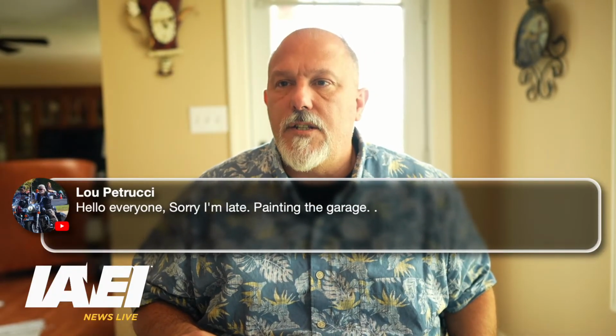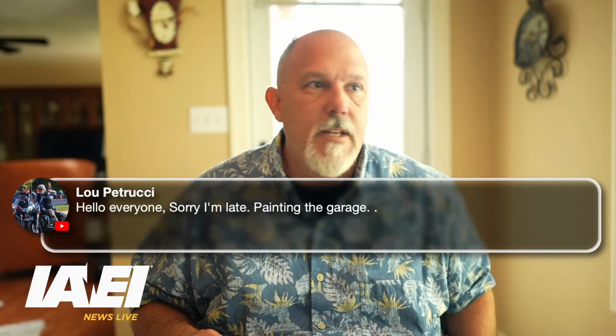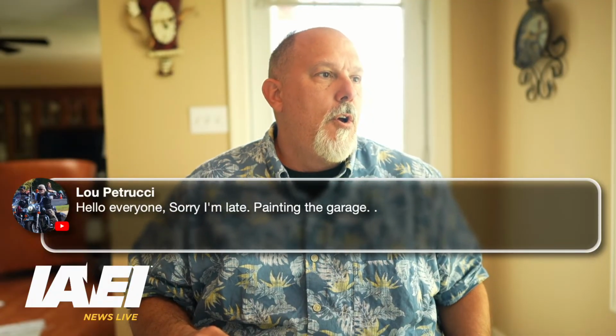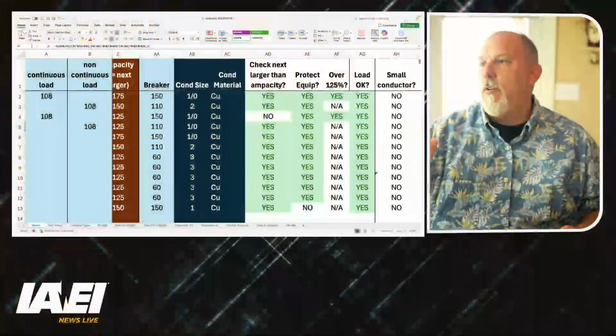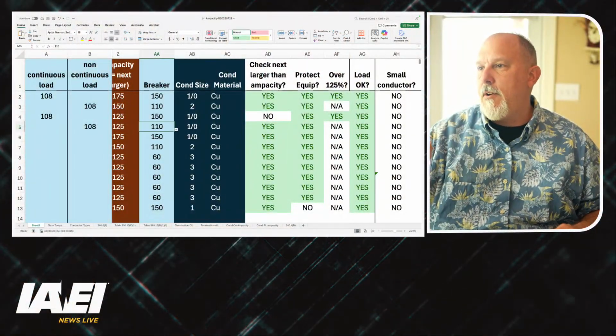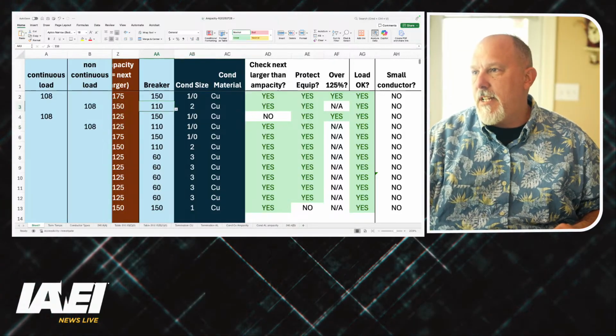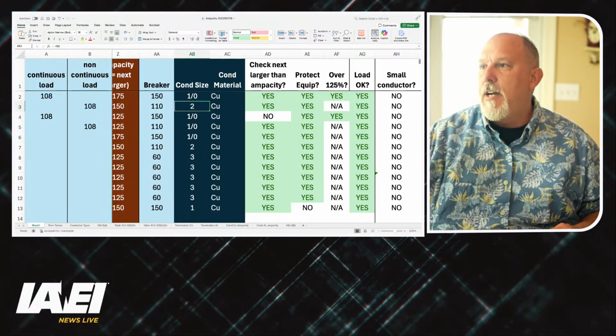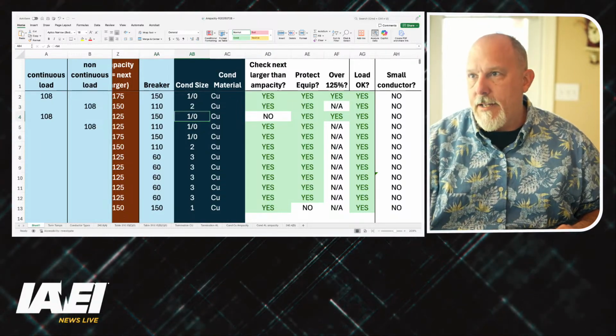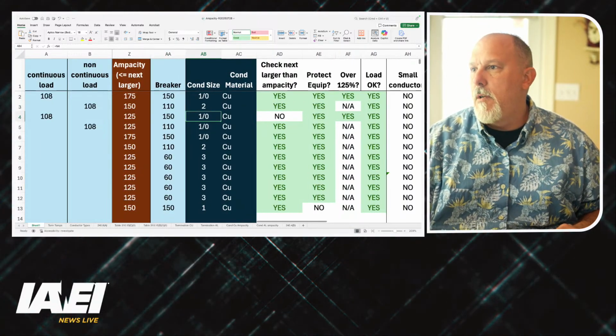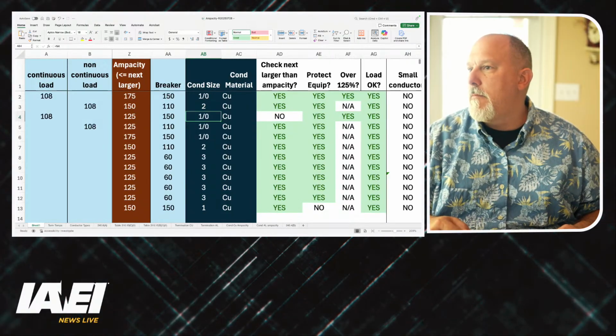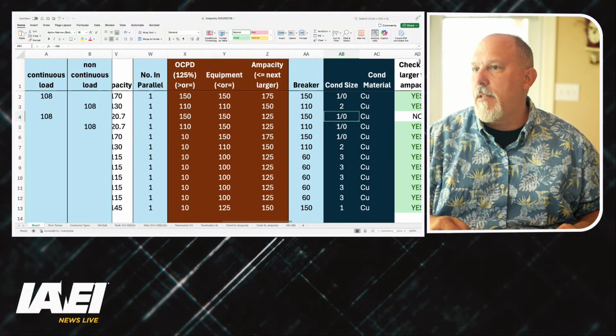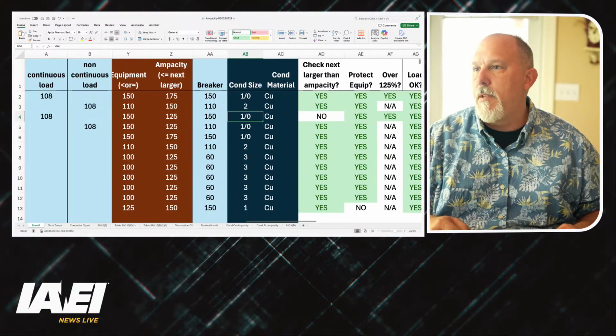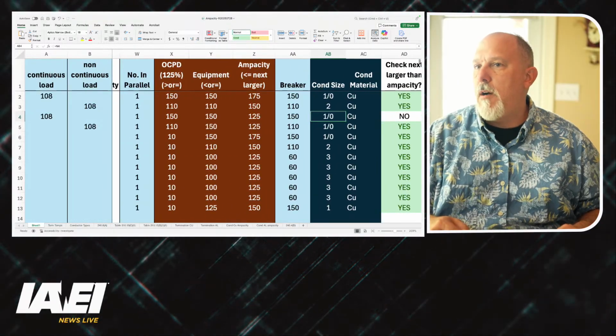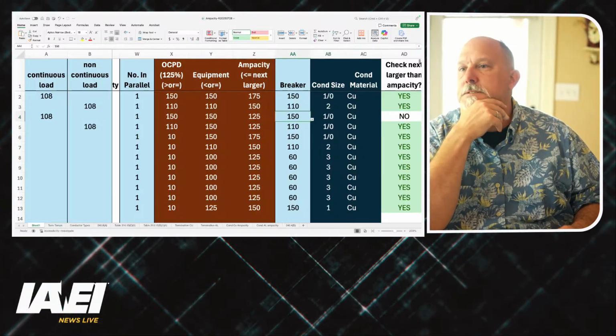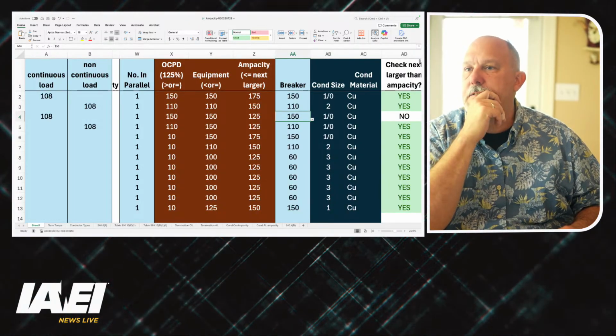Ugh. All right, so I'm going to go to UL 489. Just to refresh your memory, we have a 110 amp breaker on a 1/0 conductor, a 110 amp breaker on a 2-gauge conductor, and a 150 amp breaker on a 1/0 conductor. Hold on, what's this say? It says, oh boy, wait a second. Oh, I can't use 150. I've got to use 125.